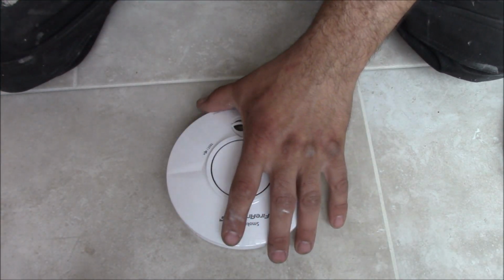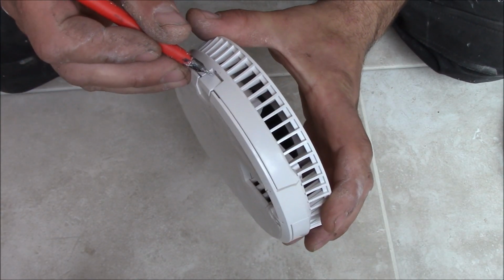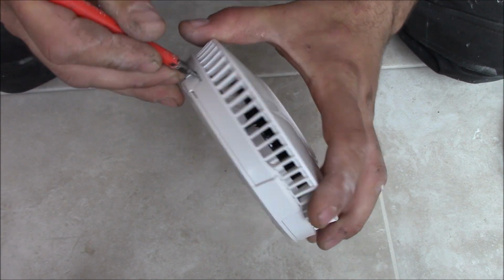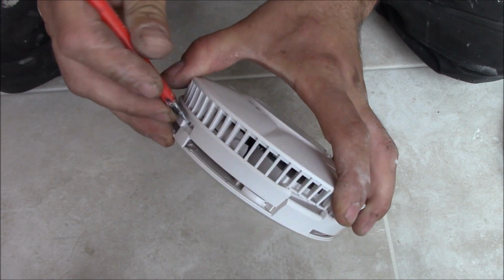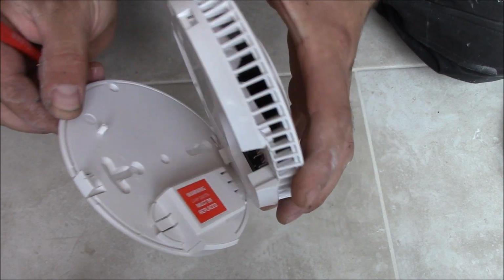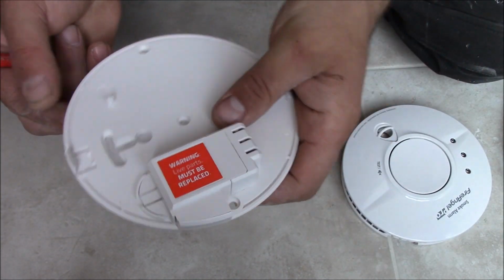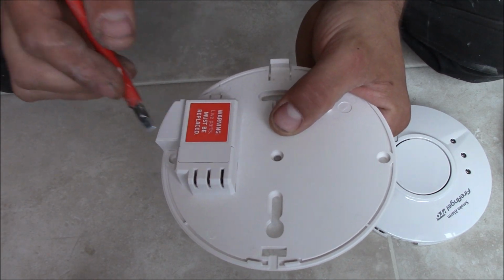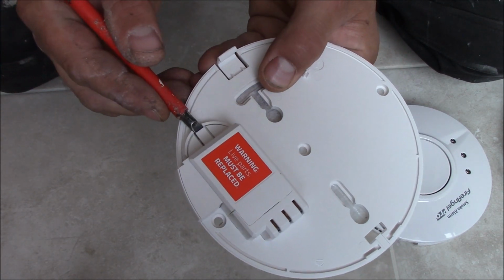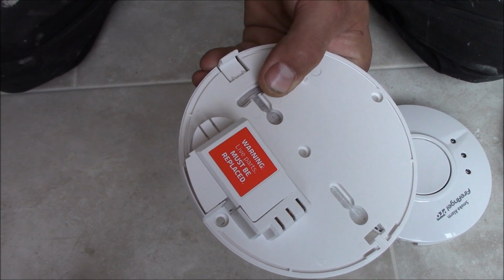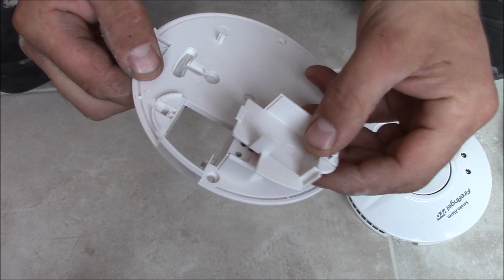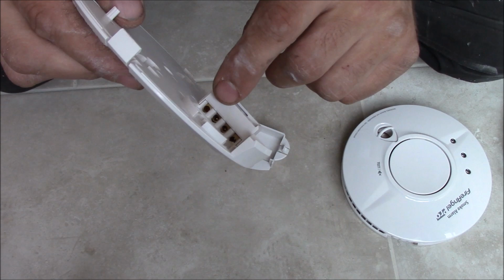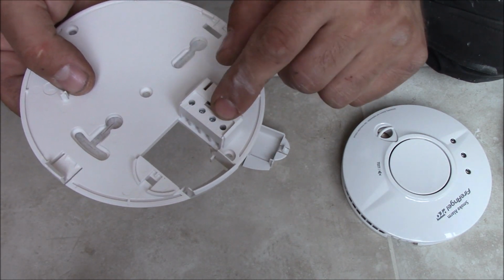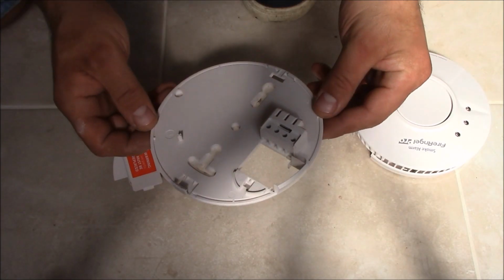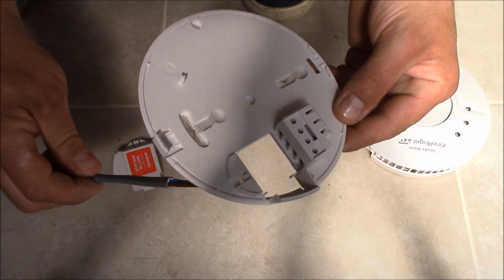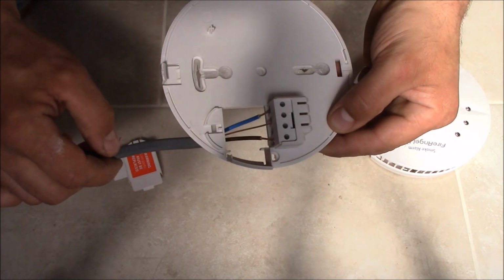So first we need to open the smoke alarm to get to the terminals. As you see, here is a small clip. Just pull it with a screwdriver. Then the terminals are hidden here. So another help with the screwdriver. And here are the terminals. Here are the screws for the terminals. First thing, when you screw this to the ceiling, obviously all the wires come through this hole into these terminals.